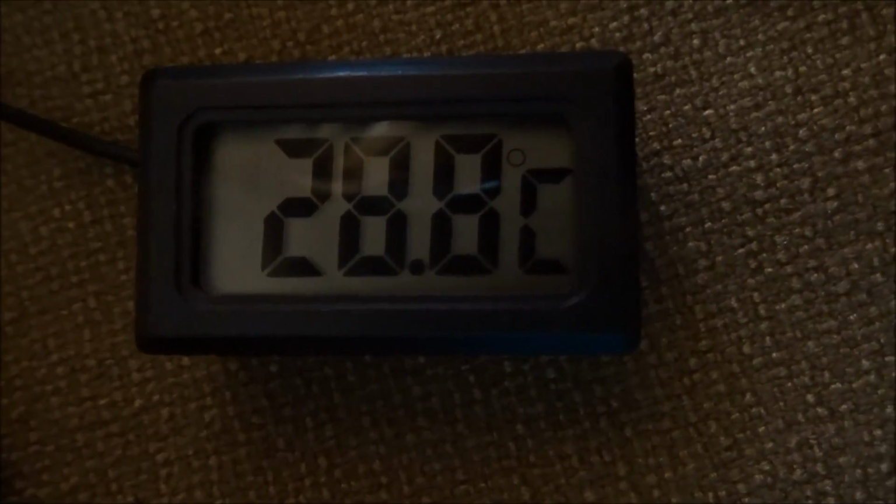So it would recirculate air, so it would actually start pulling way more amps than it should, and the compressor would shut down because of the thermal protection that it has. Outside temperature is between 28.8 and 29 degrees Celsius. So I called it 84 degrees, so it's not too hot.